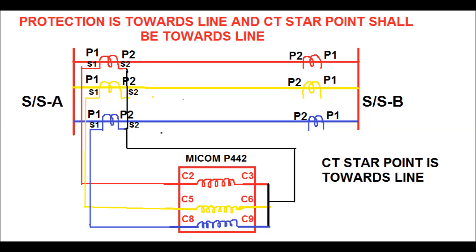In the primary side, P1 shall be connected on the bus side of the substation. In the secondary side, S1 terminal shall be connected with proper polarity to the relay. This is the general concept for proper polarity connection of the CT. The CT star point should be connected towards the line — that is, towards the protected object. Here, the protected object is the line.